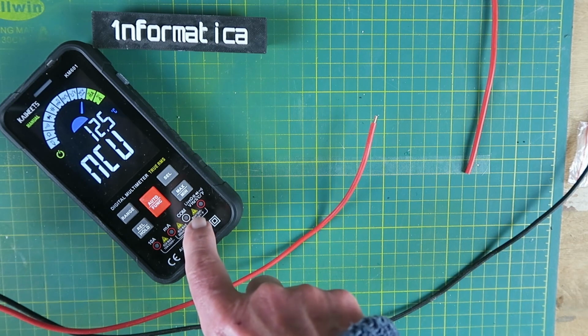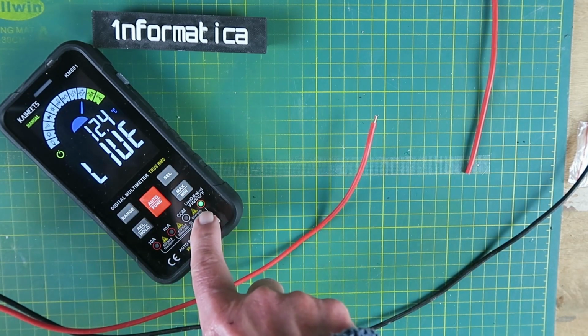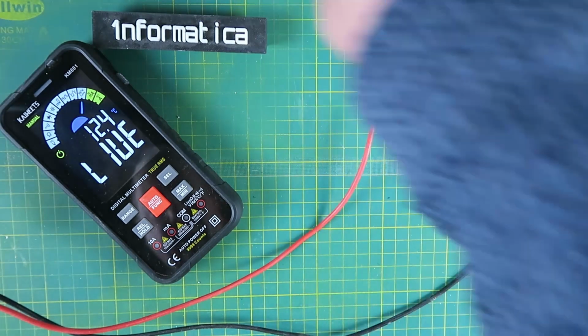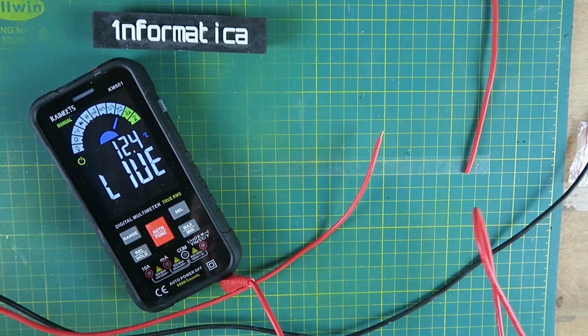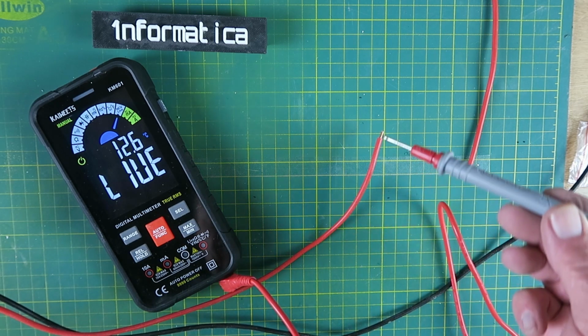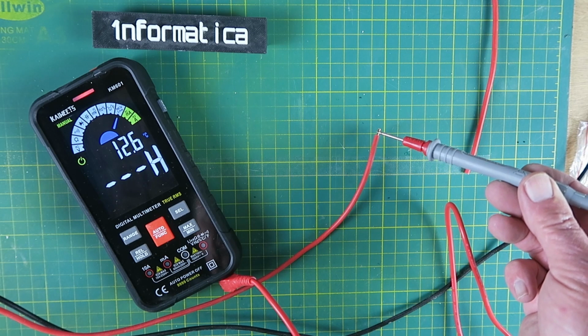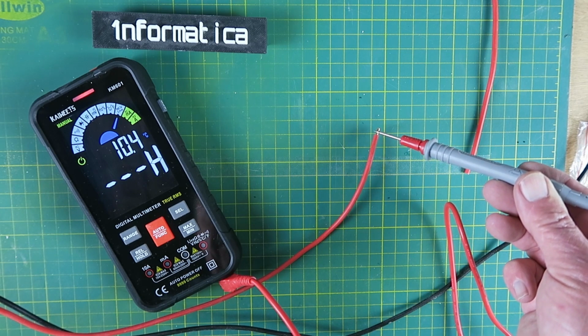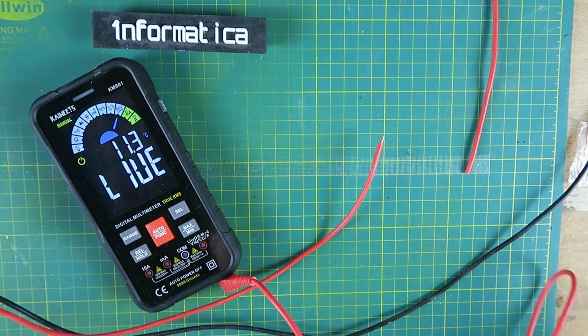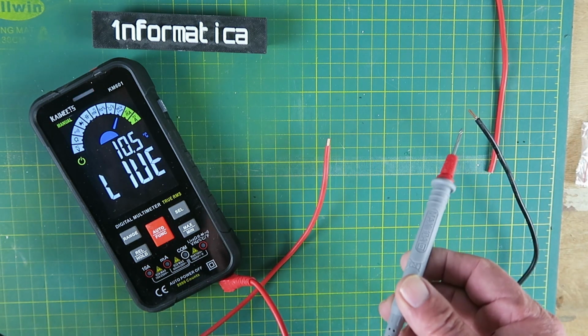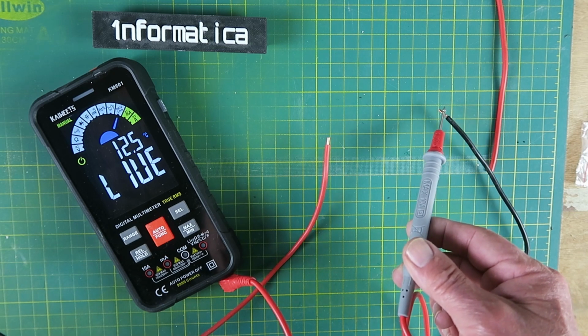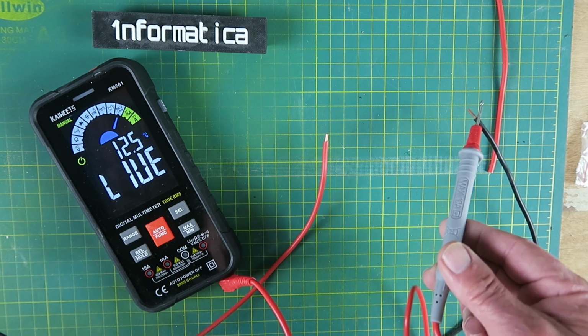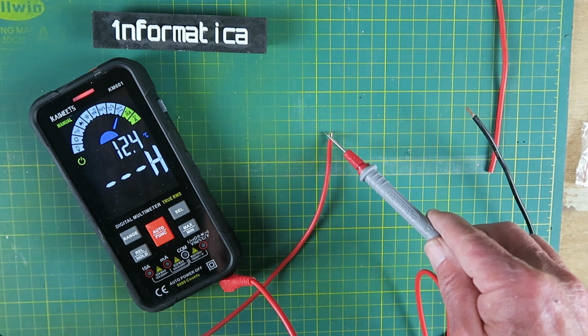The other function that it has, if we hit select, it's now looking for live and it's flashing the indicator here. If I now connect a probe to that wire and make my system live again, we can see that by touching the wire there, it is showing it is hot or high voltage, and it is indeed the live cable. And again, I stress, do not try this at home. If I touch the probe to the neutral wire, it indicates nothing. So this red wire, which should be live, in fact is. That's a good result.